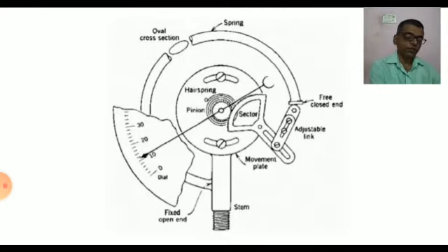The Bourdon tube is oval in cross section and one end, called the tip of the tube, is sealed and is called the free end. This is attached by a mechanical linkage to a mechanism which operates the pointer. The other end of the tube is fixed to a socket where the pressure to be measured is applied. The internal pressure tends to change the section of the tube from oval to circular, resulting in straightening of the tube.